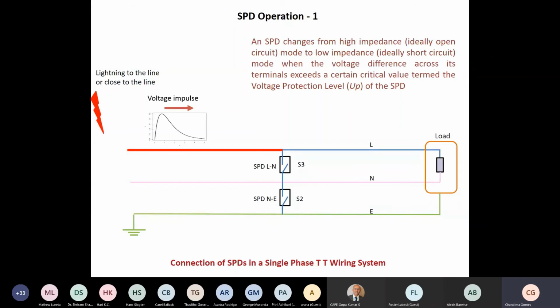Actually, in the ideal case, when it comes to the SPD, it will go from the high impedance mode to the low impedance mode, so that the current will pass into the neutral side, and a part of the current will go to the substation earth. And then this current flow into the substation earth increases the potential at one end of SPD S2, and then it will operate, sending the current into earth.